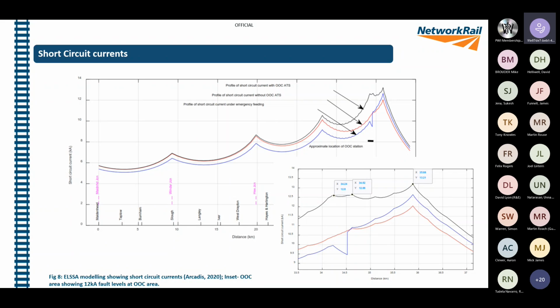ELSSA modeling was done to identify the short circuit currents and the impact of adding an additional ATFS on the route. As shown, it gives a 12 kA fault level, the highest for that area, occurring closer to where the auto transformer feeder station will be installed. This means the OLE needs to be robust enough to withstand that level of fault, to avoid any derailment. So the overhead line equipment used for the station area is UKMS 100 with 107 contact wire, which is categorized as able to comply with 12 kA requirements.